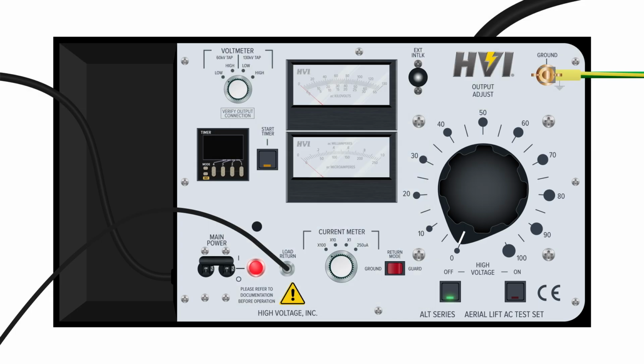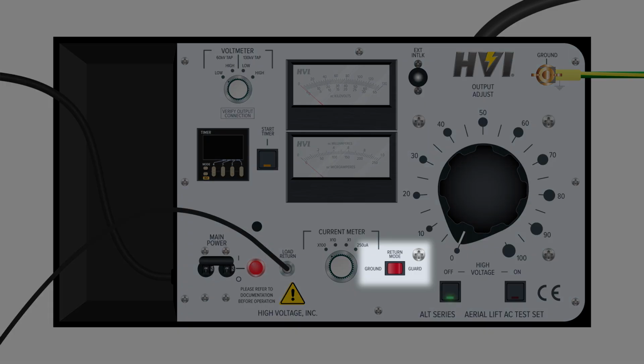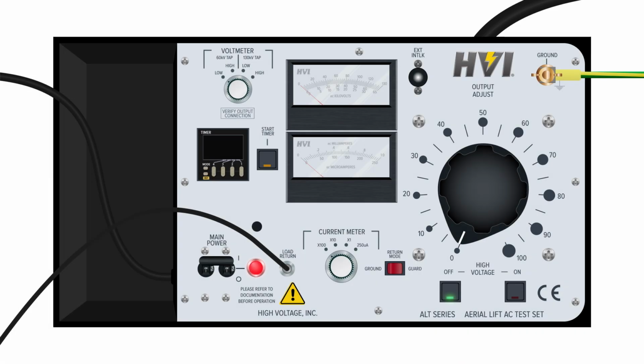For tests such as these, follow all the basic setup and safety checks you would for a test with grounded return. Recheck all your safety provisions and your cable connections. Turn the control panel unit on and set your timer. Before activating the high voltage circuit on button, change the return mode switch over to guarded return. Now, run the test for the intended duration, the same way as shown before for grounded return mode. When the timer sounds, power down the unit.